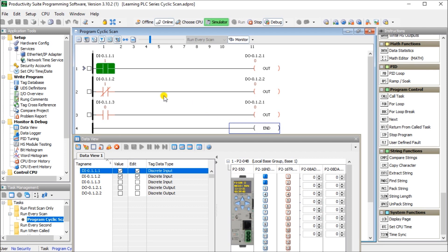What you'll see is that when I have two outputs, it's always the last output that gets triggered. Sometimes when you're troubleshooting PLC logic, moving a rung to the end of the program will make it function. You can then look for duplicate outputs in your ladder logic code.